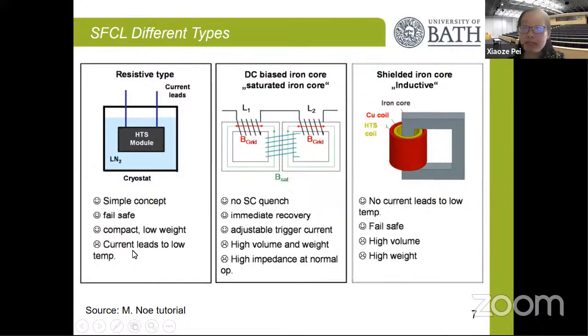But one of the biggest challenges is that the superconducting tape and module sit in liquid nitrogen, and they have to have current leads which connect the room temperature to the low temperature environment. Considering high voltage application, the design of these current leads is one of the biggest challenges for the resistive superconducting fault current limiter.